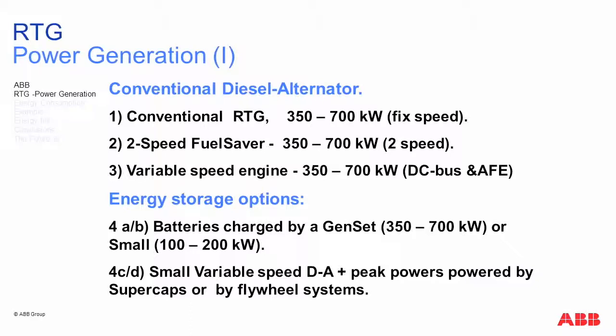The second group is RTG with energy storage option. This can be done in 2 ways: with batteries, or with other types of storage like supercaps or flywheel. The battery-fitted RTG could have a full-size genset diesel generator of 350 to 700, or a small diesel engine of 100 to 200 kilowatts just to charge the batteries.